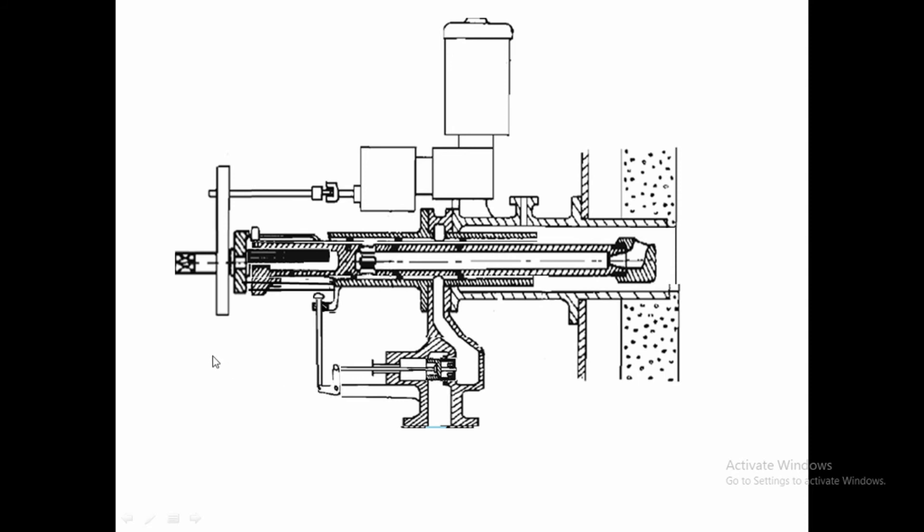As the handle is pulled down by this valve actuating mechanism, it pulls out the double seat valve. And the steam goes into this point and through the steam ports goes into the spindle and the nozzle, and the steam passes through the nozzle and impinges on the sooted portion of the tubes.